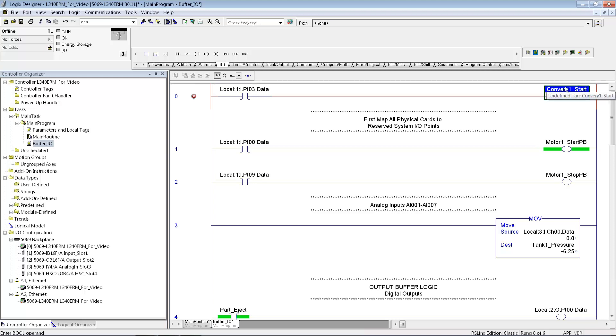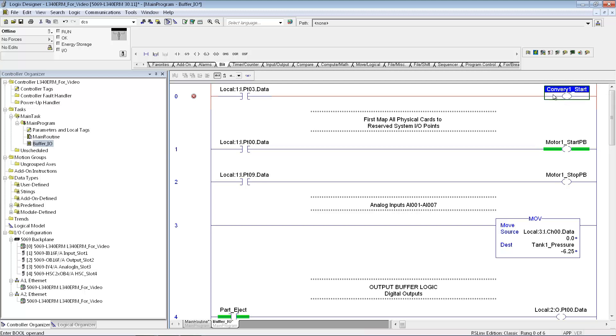Maybe this one is conveyor one start. I can make these up to, I believe, 48 characters long. Typically you're better off not getting too carried away with the length that you make in these tags, but you can make them up to 48 characters. One thing I also like to do is start out with a capital letter, and every place you're going to another word, for instance I'm going conveyor one, and then start, I capitalize the S for start. It just makes it a little easier to read the program.